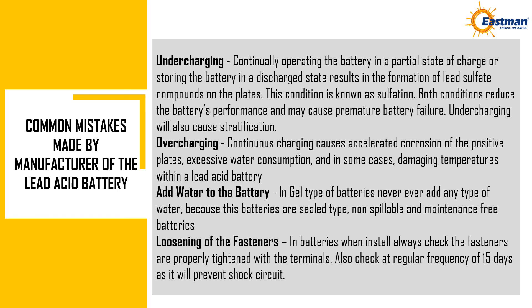Common Mistakes Made with Lead Acid Batteries. Undercharging: Continually operating the battery in a partial state of charge or storing it in a discharged state results in the formation of lead sulfate on the plates (sulfation), reducing performance and potentially causing premature failure. Undercharging also causes stratification. Overcharging: Continuous overcharging causes accelerated corrosion of the positive plates, excessive water consumption, and damaging temperatures. Adding water: In gel-type batteries, never add any type of water, as these are sealed, non-spillable, maintenance-free batteries. Loosening of fasteners: Always check that fasteners are properly tightened at terminals during installation, and re-check every 15 days to prevent short circuits.